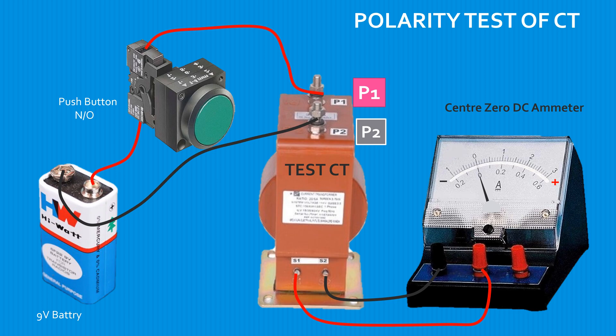Now when you press the test push button, if the pointer of the ammeter deflects to the positive side of the scale, then the assumed S1 and S2 are correct in polarity. Mark them permanently.